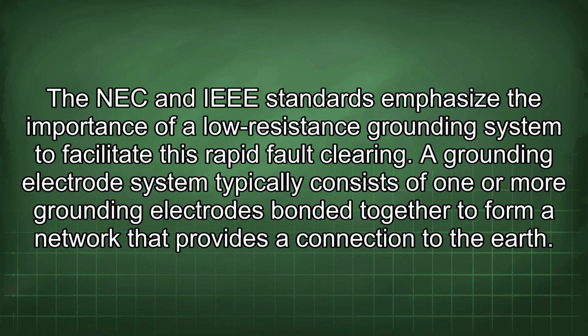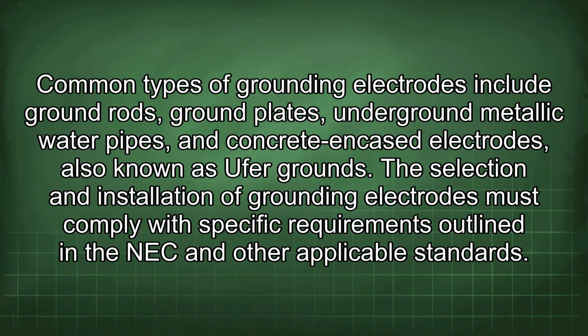A grounding electrode system typically consists of one or more grounding electrodes bonded together to form a network that provides a connection to the earth. Common types of grounding electrodes include ground rods, ground plates, underground metallic water pipes, and concrete-encased electrodes, also known as Ufer grounds. The selection and installation of grounding electrodes must comply with specific requirements outlined in the NEC and other applicable standards.